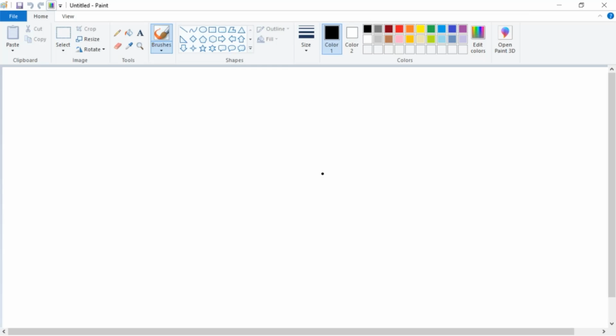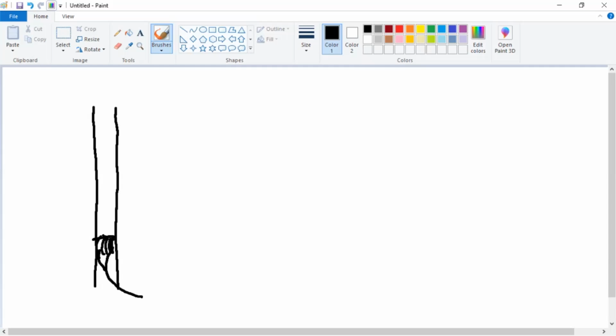Okay. The other method of doing an installation. I'll do the first one that they've got over here. Here's my primary cable. They've got the jacket down here and they've got grounds coming down, tied into the transformer at the bottom. Then they've got their strands that go up to the elbow. We would take the strand, either one or two strands, and make a loop, and then make the connection up here, and the fault indicator would go on. That's one legal way of doing it.